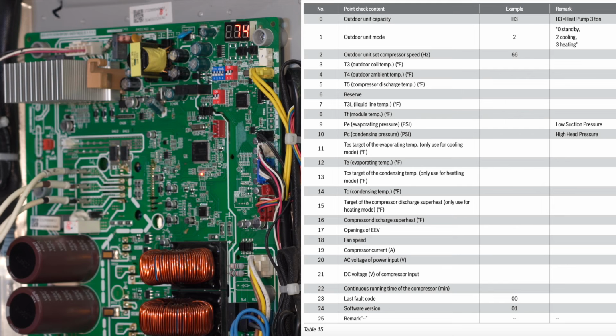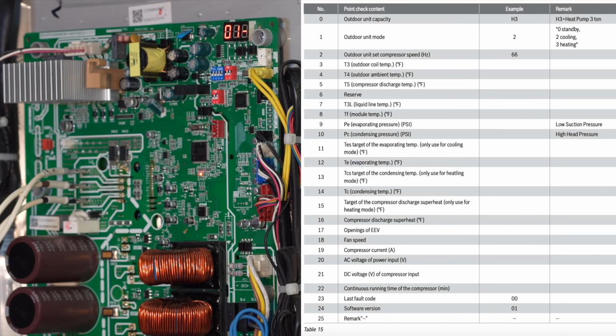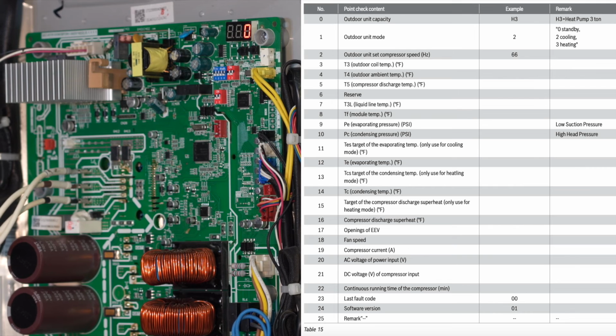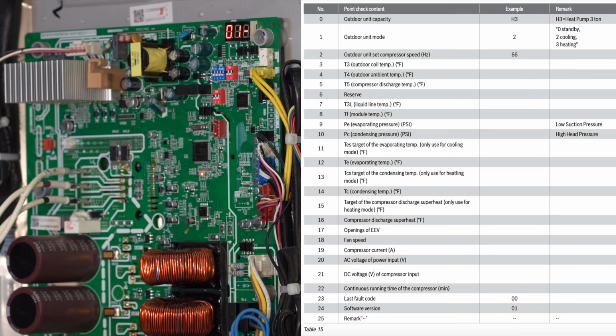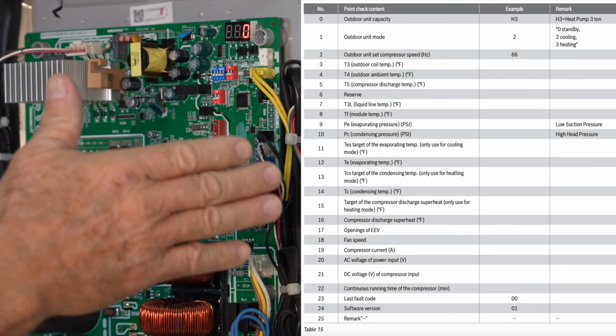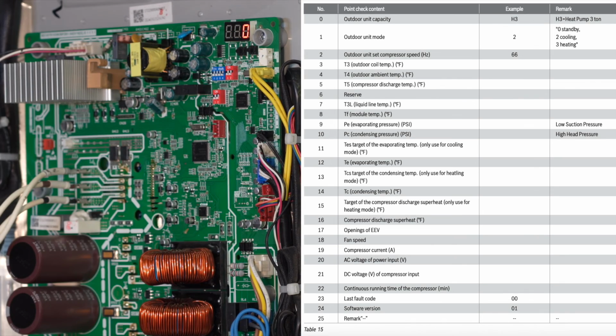Oh, I don't have to go to my voltmeter. Let's just push a button twice. 1, 2, and look what we have. There's a 0, meaning that I satisfied the thermostat, board went off, air conditioner went off. It is as simple as that. There's no call at this point. If it was calling for cooling, once again, it would be a 2. If it was calling for heating, it would be a 3.